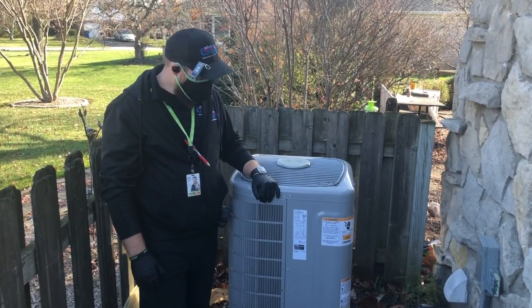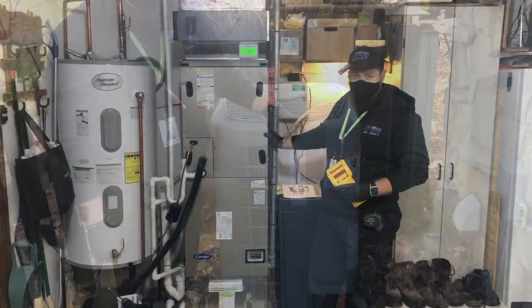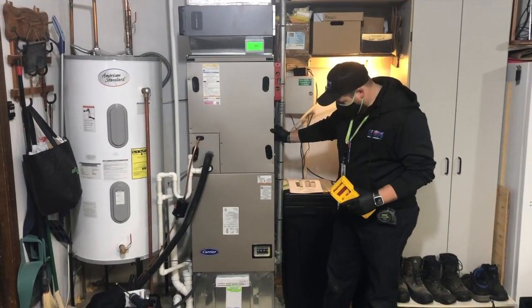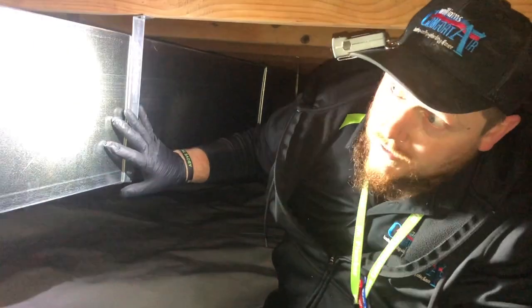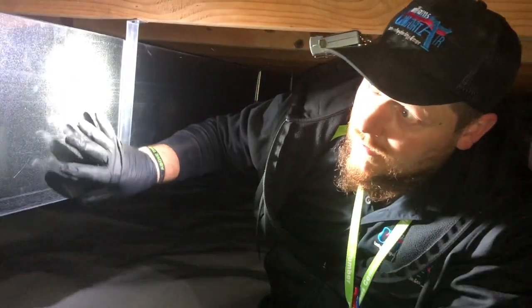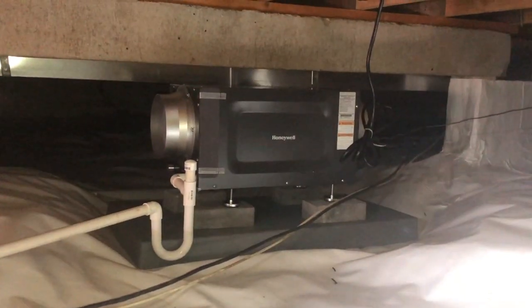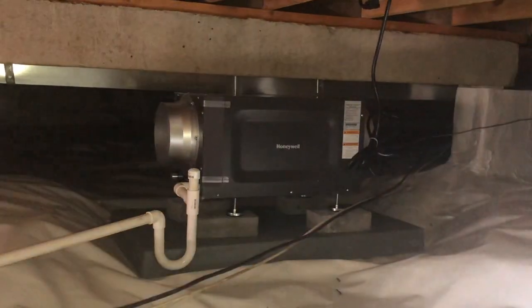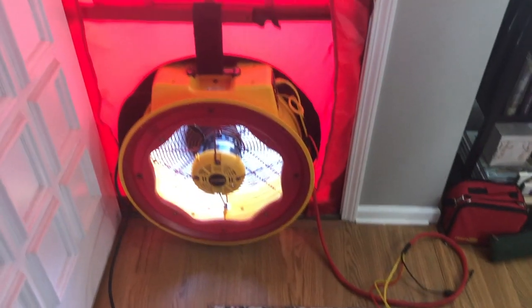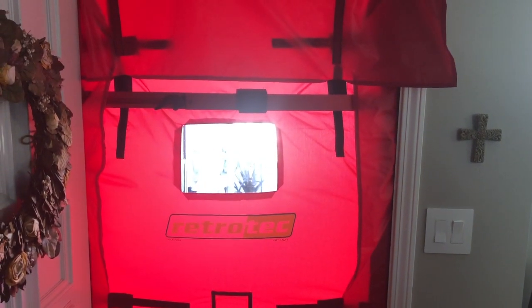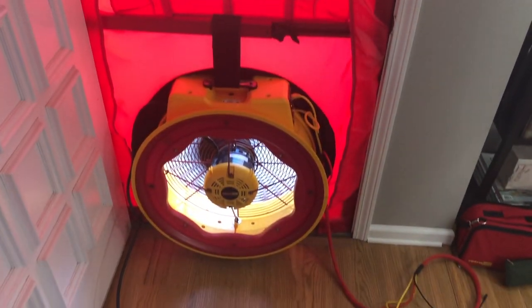Well, as you can see, we did quite a bit of work on this project. The new variable speed equipment was working great. The new sealed ductwork was providing even temperatures throughout the house. The humidity was under control. An air device test showed vast improvements in all of the air quality. It was now time to do another blower door test to see how much of the infiltration and exfiltration had been eliminated.